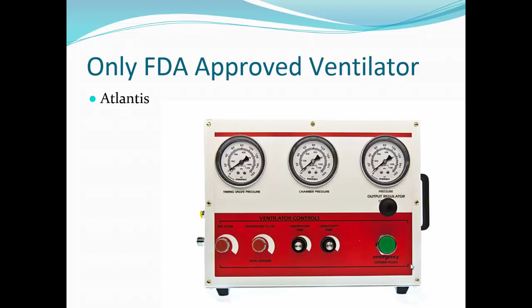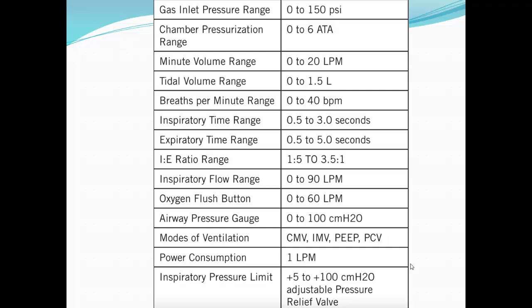In the U.S., we have one FDA-approved ventilator, the Atlantis. You can see it there, and these are all the specs of it. You can see it basically ranges the whole gamut of what you would need on a ventilator. It works up to 6 ATA, 20 liters per minute for minute ventilation, up to 1.5 liters of tidal volume, up to 40 breaths per minute. Variable I times, E times, setting your I:E ratio, etc., and different modes of ventilation: CMV, IMV, PEEP, and PCV.